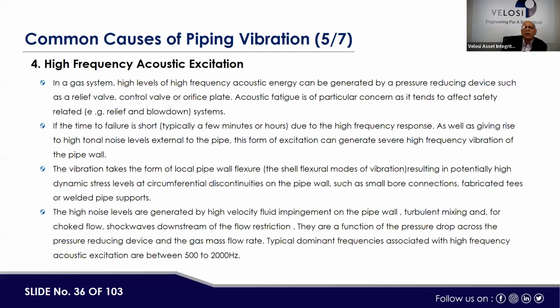Similarly, there is flashing, which causes high excitation, or high acoustic excitation, as we call it. That is when steam condensate from a high pressure steam system is mixed with the medium pressure or low pressure condensate system, then flashing may occur there. And that flashing can also cause high erosion as well as high vibration and noise in the system.